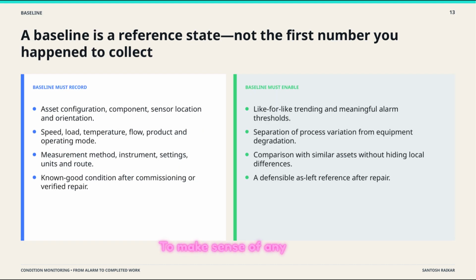To make sense of any data, you need a baseline. A baseline isn't just the first number you recorded. It's a record of a known good state. It must include the asset configuration, operating speed, load, and the specific measurement method.